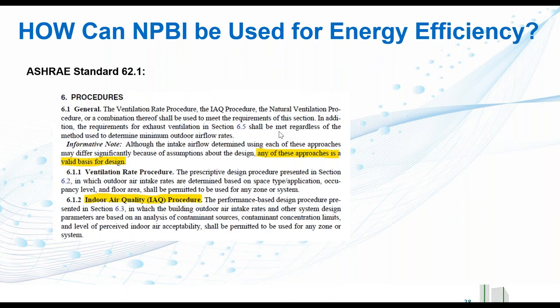How can we use it for energy efficiency? As was covered in the beginning of the presentation, April mentioned it, good ventilation is important. And ASHRAE standard 62 defines how the amount of outside air for any given space based on people and occupancy is determined. In the standard, there are different procedures that are allowed to be used. The ventilation rate procedure is the one that we see used most commonly by design firms.